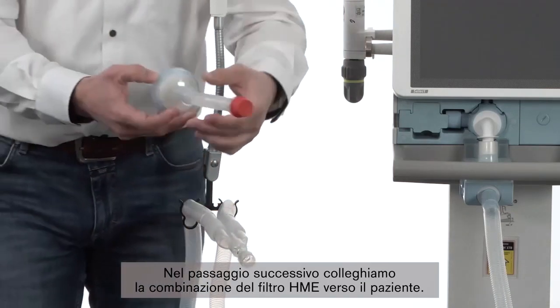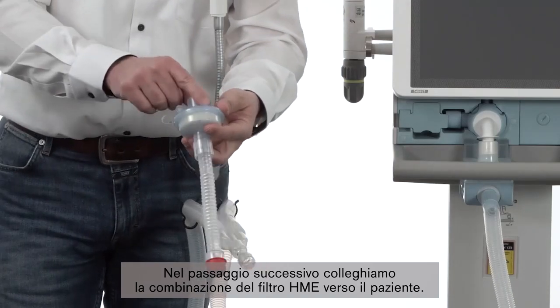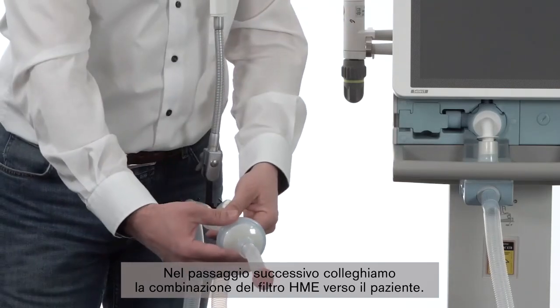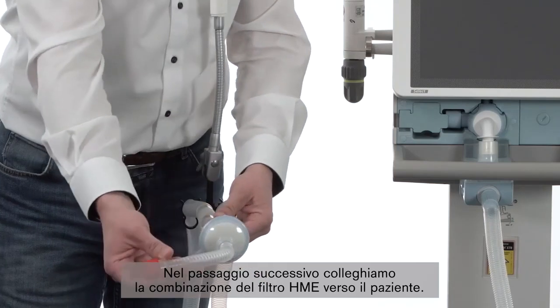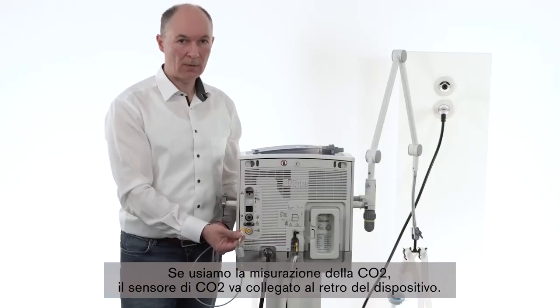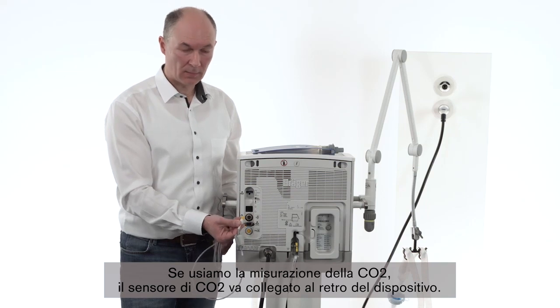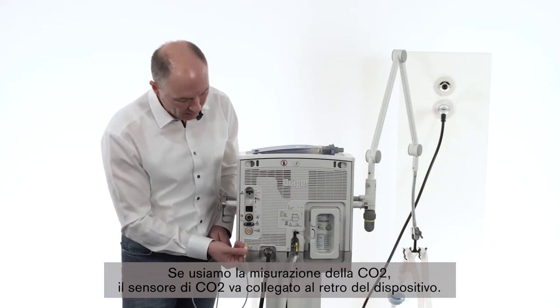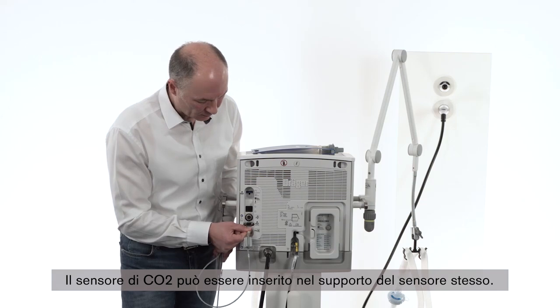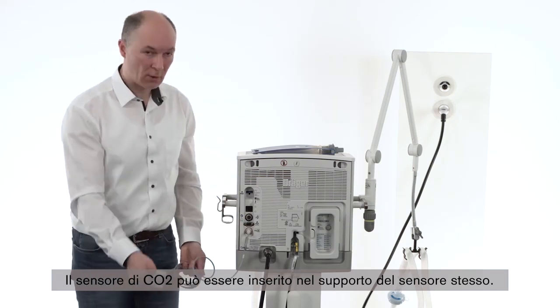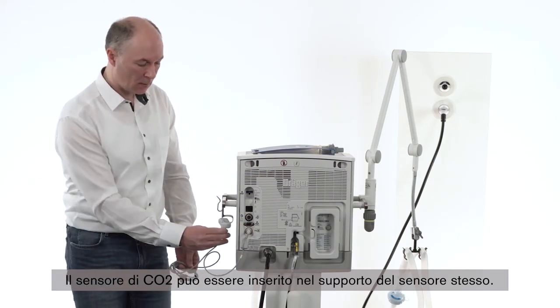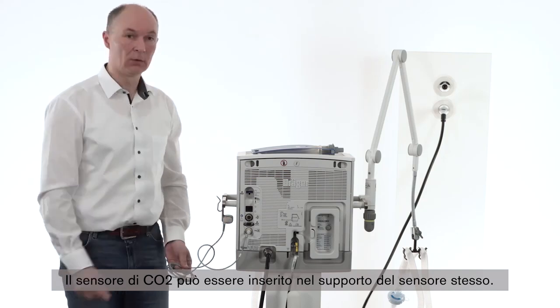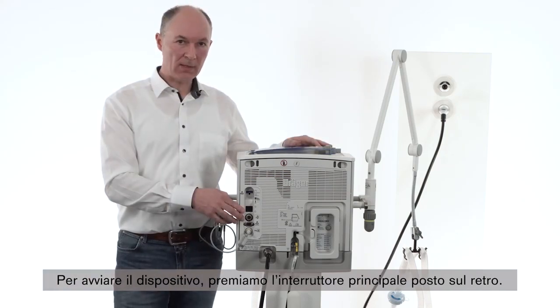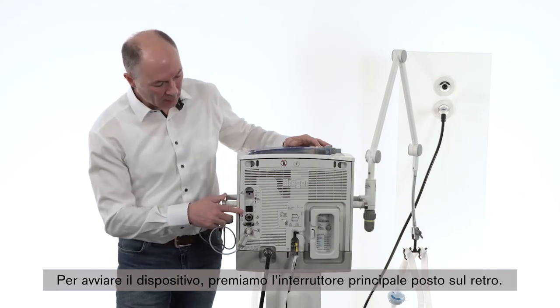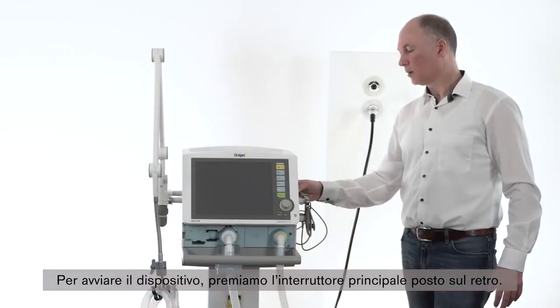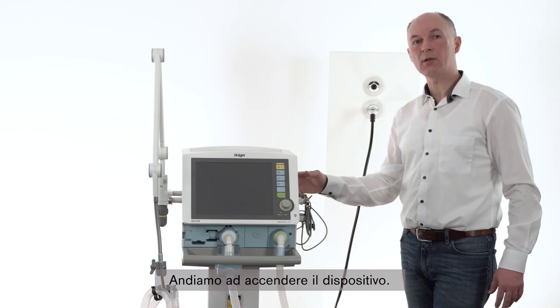In the next step, we are attaching the filter HME combination towards the patient. In case you are using the CO2 measurement, please connect the CO2 sensor at the back of the device. The CO2 sensor can be placed in its CO2 sensor holder. To start the device, use the main switch on the back of the device. And at the back of the device, we are turning the device on.